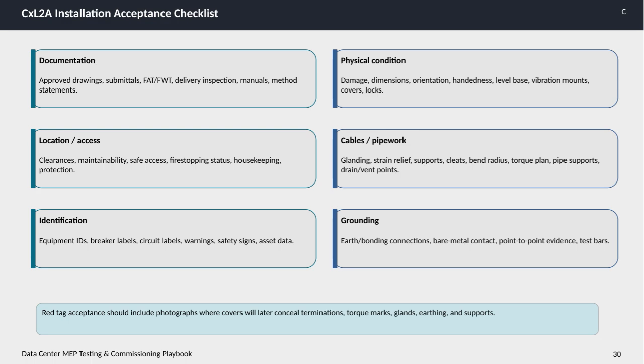Next, physical condition involves checking for any damage, verifying dimensions and orientation, assessing handedness, ensuring the base is level, and confirming vibration mounts, covers, and locks are properly installed and secure. These checks help guarantee the equipment will function correctly and safely. For location and access, we verify that clearances are adequate, maintenance can be performed safely, fire stopping is intact, housekeeping is maintained, and the equipment is properly protected. This ensures the environment supports both operation and safety requirements.